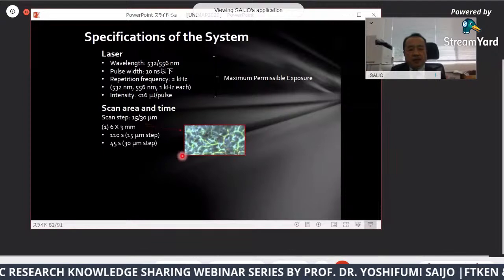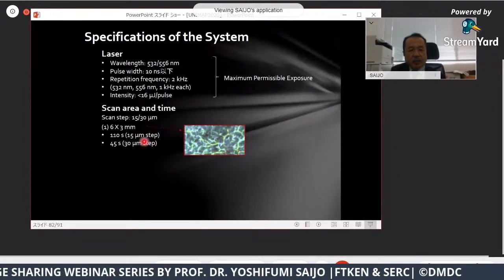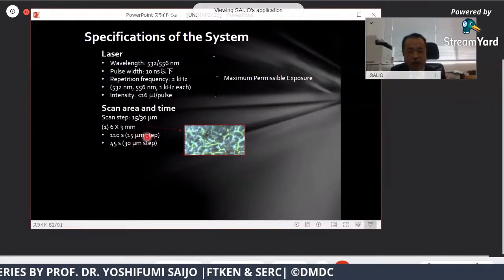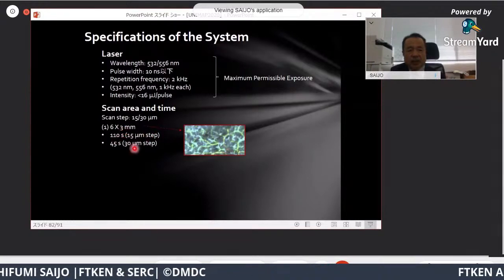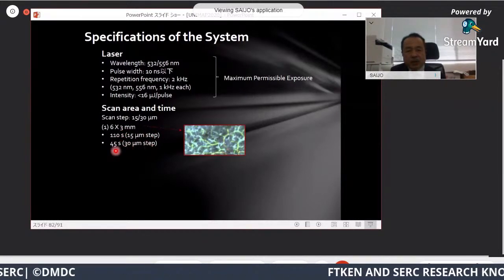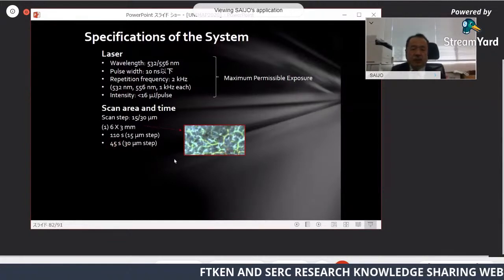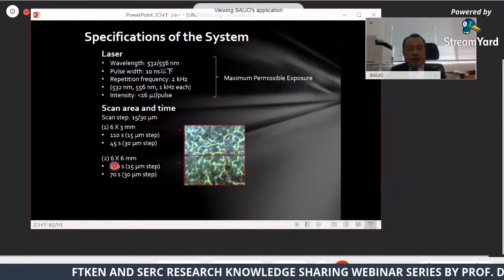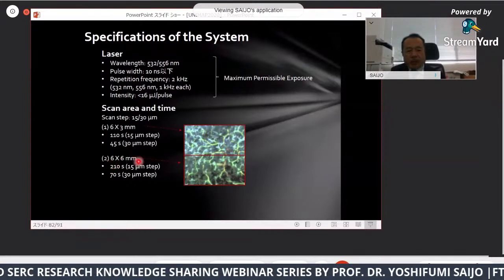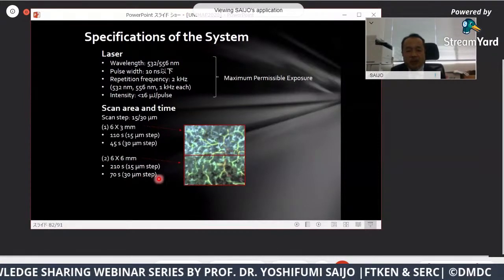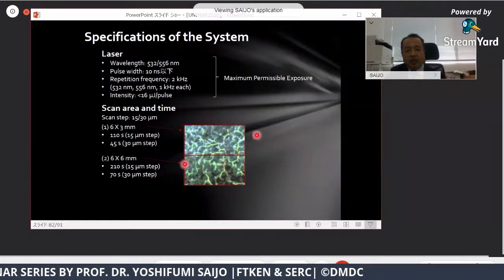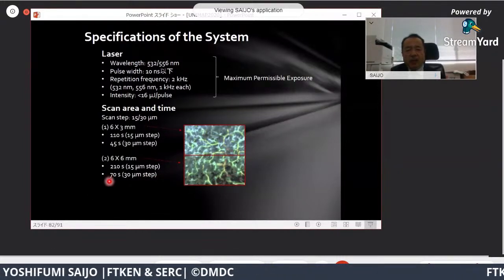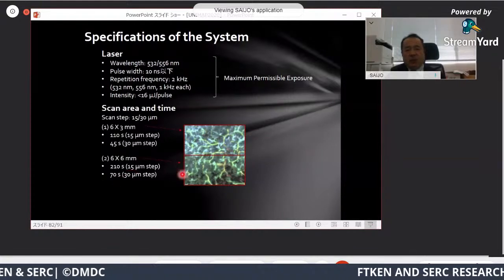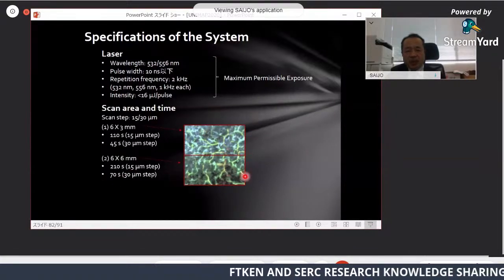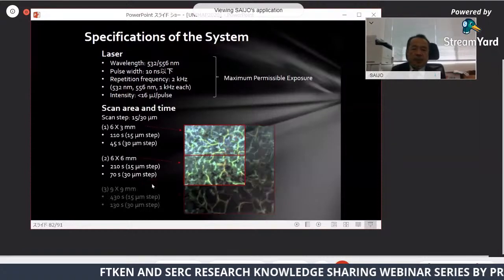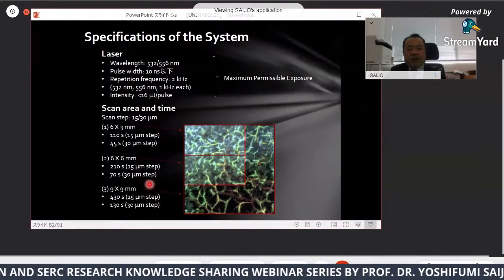And one is 6 and 3 millimeters. And at that time, if we use a 15 micron step, it takes 110 seconds. And if you use a 30 micron step, it takes 45 seconds. And in case of 6 by 6 millimeters, using the 30 micrometer step, actually this image was taken by the 30 micrometer step. It takes almost 70 seconds, almost 1 minute, to visualize 6 millimeters. And the 9 by 9 is almost 2 minutes.